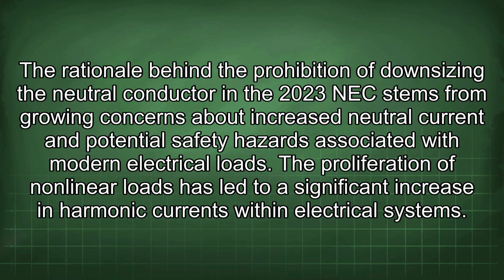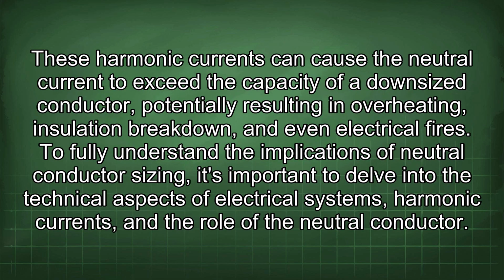The rationale behind the prohibition of downsizing the neutral conductor in the 2023 NEC stems from growing concerns about increased neutral current and potential safety hazards associated with modern electrical loads. The proliferation of nonlinear loads has led to a significant increase in harmonic currents within electrical systems. These harmonic currents can cause the neutral current to exceed the capacity of a downsized conductor, potentially resulting in overheating, insulation breakdown, and even electrical fires. To fully understand the implications of neutral conductor sizing, it's important to delve into the technical aspects of electrical systems, harmonic currents, and the role of the neutral conductor.